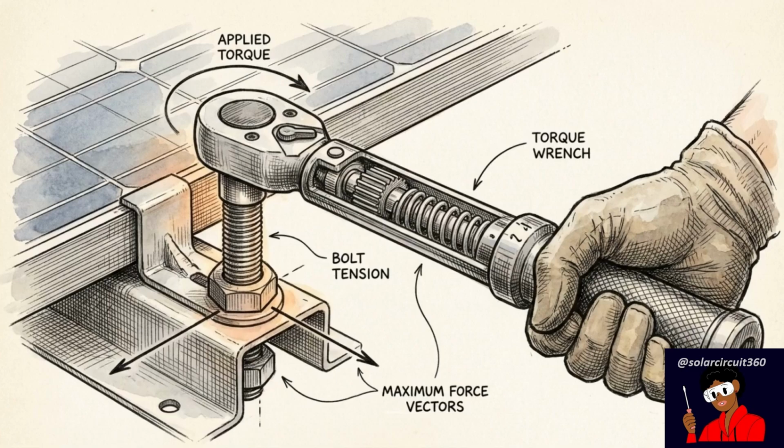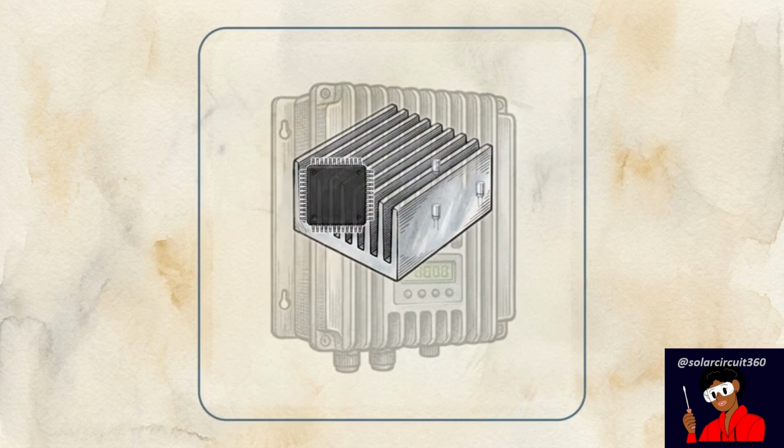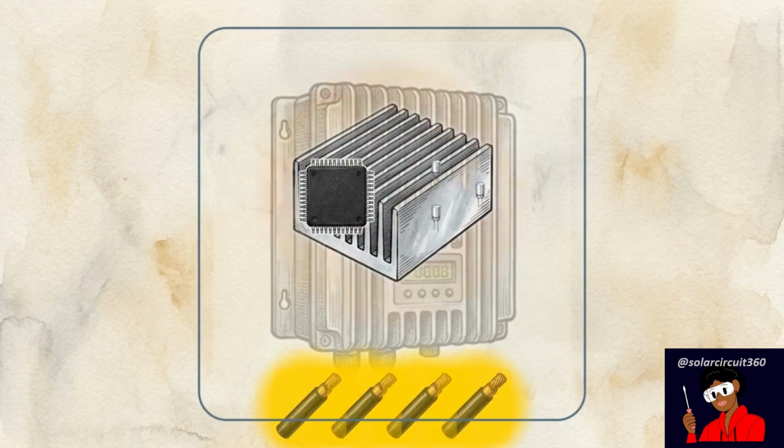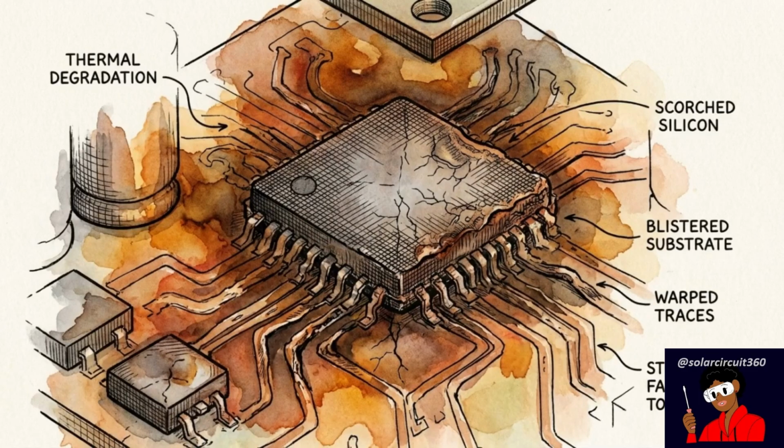capital investment. Beyond the lost kilowatt hours, this sustained daily clipping results in severe physical degradation deep inside the actual hardware. Continuous current limiting has physical consequences. Resisting electrical flow generates immediate and sustained internal heat. For the entire 2-hour peak window, localized heating places severe thermal stress on the solid-state components inside the enclosure. This forces a state of thermal derating. The inverter detects the internal temperature spike and reduces its operating efficiency further just to survive the heat.